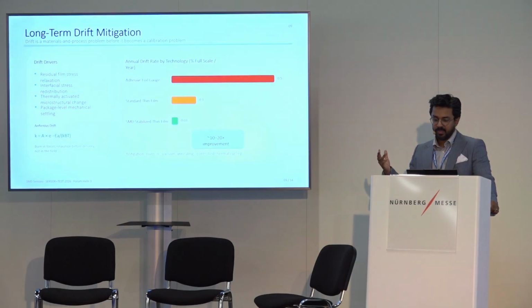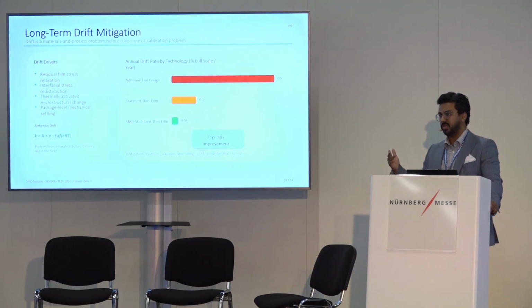So just to mitigate that residual film stress, what can be done is before sending out these sensors, you can anneal them in-house. You can deliberately vacuum anneal them in the factory, and age them and calibrate accordingly. If that process exists, it eliminates all of the residual stress that appears over a long period of time. So when designing the sensors, you must keep in mind that these drivers are super important, and that has to be established into the manufacturing stage in quality, and calibrated and certified according to certain standards. For aerospace, it would be AS standards. For medical, it would be ISO grade standards, and it has to be calibrated accordingly. In the US, we follow that. And in-house, we have that calibration capacity.